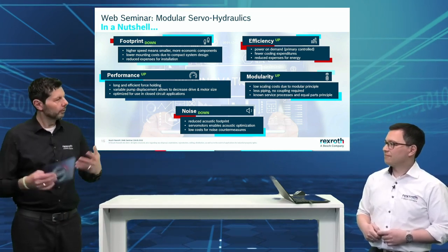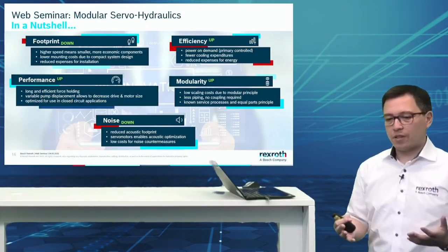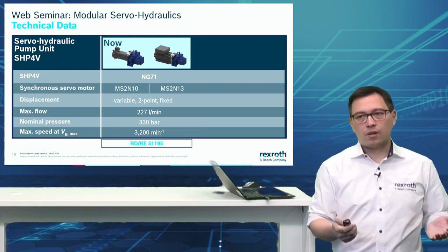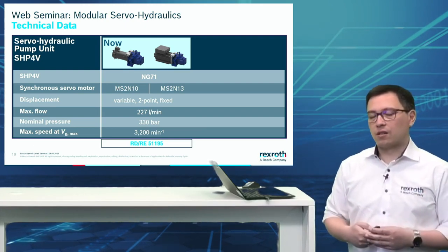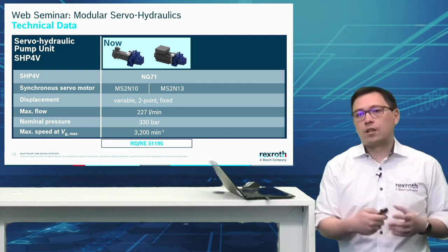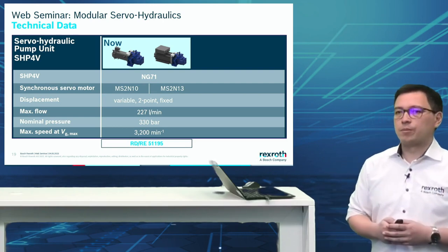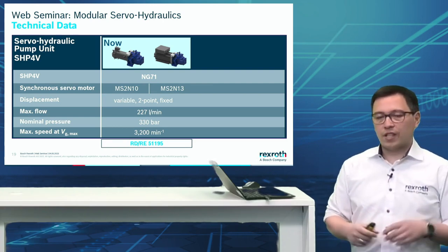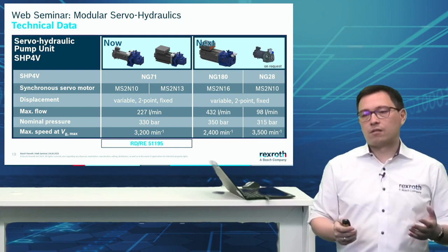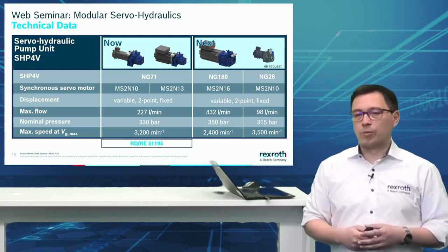Now, as a product manager, let's talk about the product offering. We explained the trend, how we answer and shape it — and we actually heard the machine. But what does it do? What are its key characteristics? The SHP 4V servo hydraulic pump unit comes with a nominal size of 71, with two types of synchronous servo machines — size 10 and 13 — with variable two-point or fixed displacement. The data sheet link will be in the description. What comes next is roughly twice the size and half the size: nominal size 180 and nominal size 28.